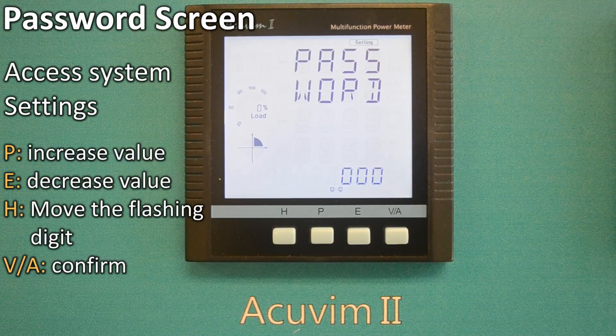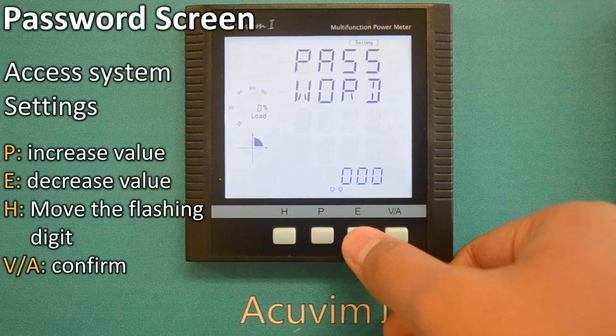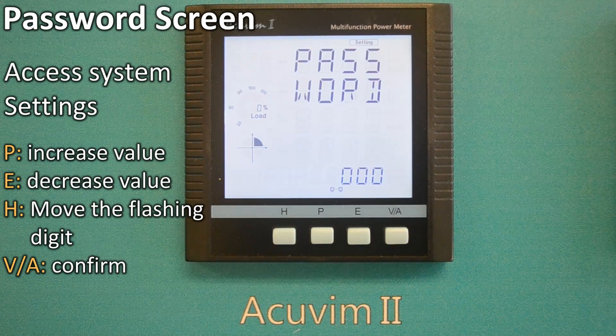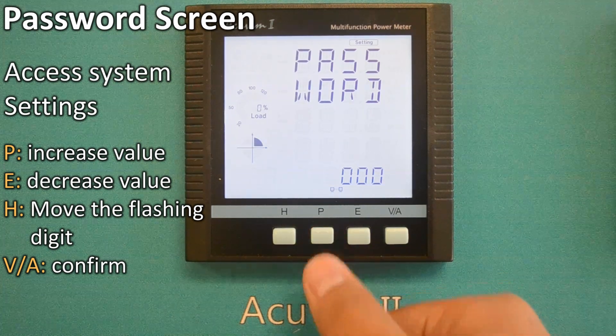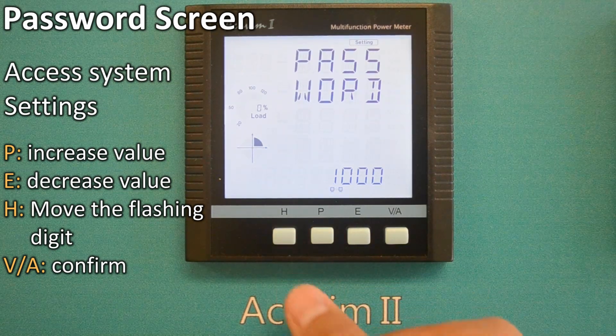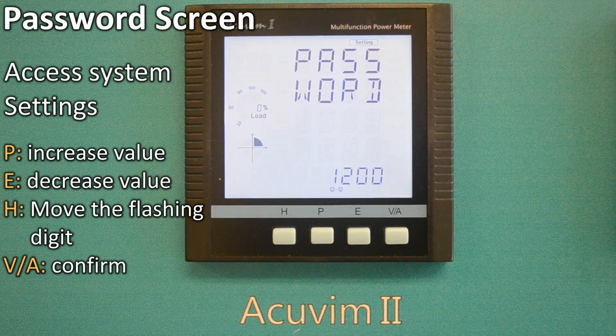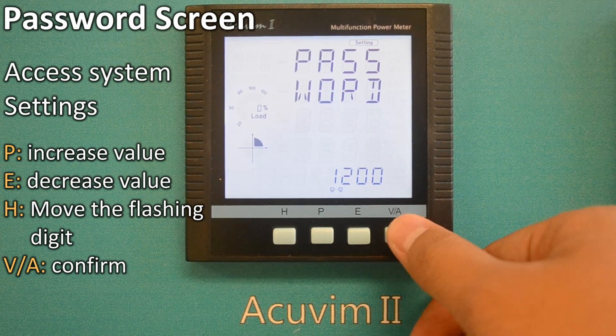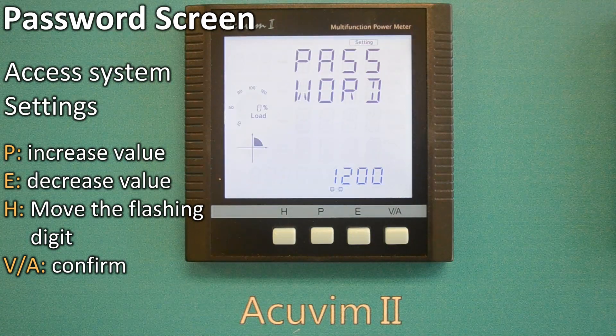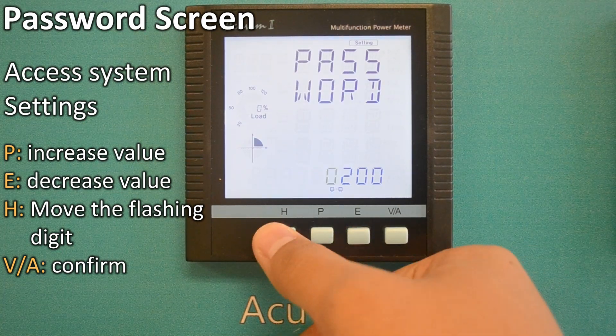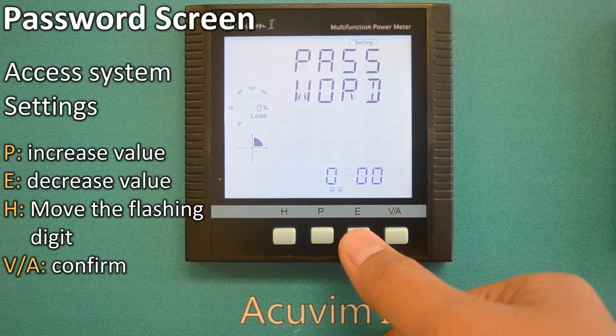To enter the password, press P to increase the value, E to decrease the value, and press H to move the flashing digit. For instance, if your password is 1200, press P to change the first digit to 1, press H to move to the next digit, and push P to change the value to 2. When you finish inputting your password, press the VA key to confirm. If an incorrect password is entered, the screen will remain. The meter's factory default password is four zeros. Press VA to confirm the password.